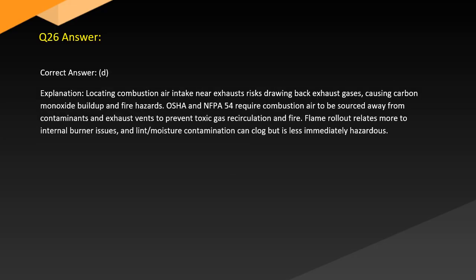Answer. Correct answer: D. Explanation. Locating combustion air intake near exhausts risks drawing back exhaust gases, causing carbon monoxide buildup and fire hazards. OSHA and NFPA 54 require combustion air to be sourced away from contaminants and exhaust vents to prevent toxic gas recirculation and fire. Flame rollout relates more to internal burner issues, and lint or moisture contamination can clog but is less immediately hazardous.